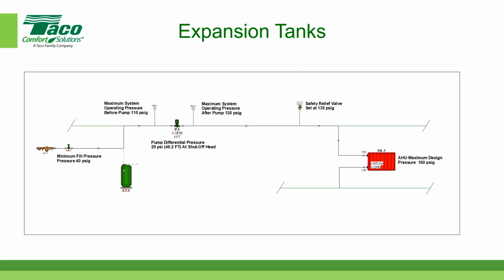And the reason is because expansion tanks can fail, bladders can fail for a variety of reasons. And if they fail and the tank fills up with water, if the tank becomes waterlogged, is the term we use, and there's no place for the fluid to expand if it heats up. If we didn't have a safety relief valve, then we'd break something in the system. So yes, we absolutely want safety relief valves.